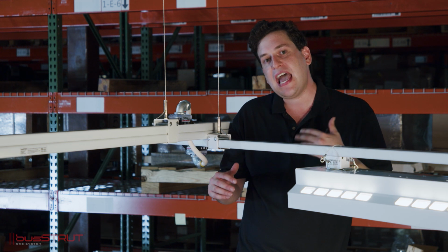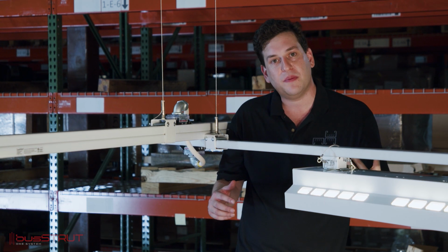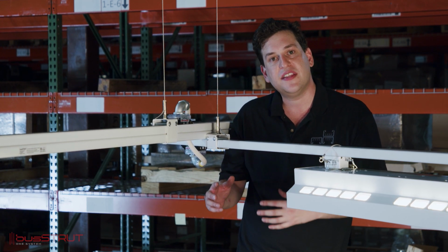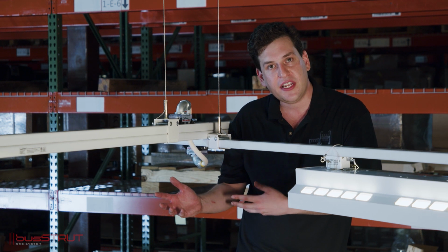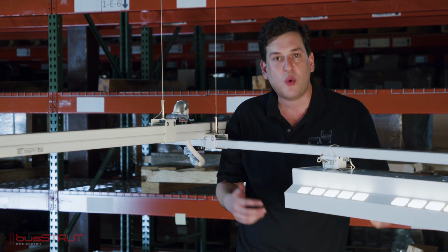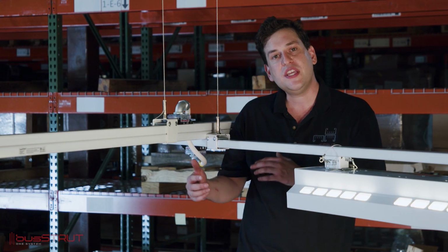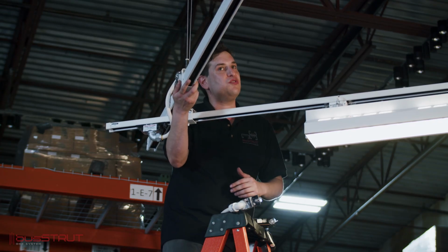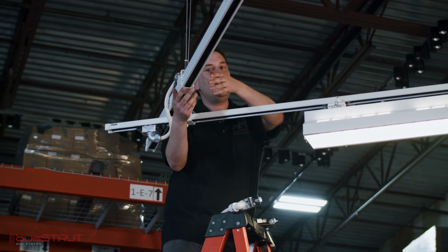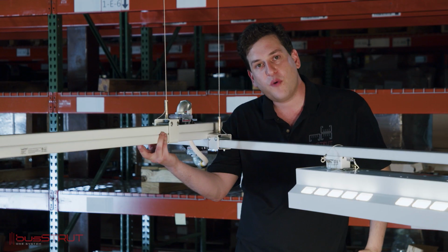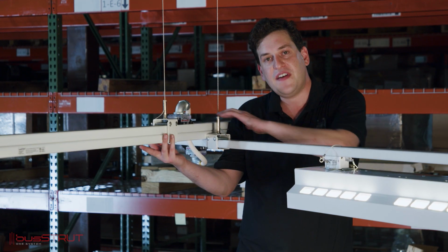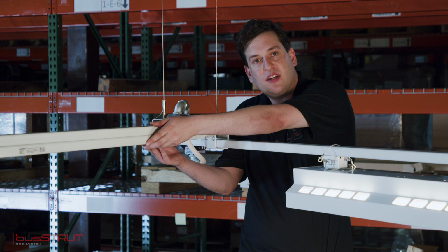But we have an added advantage as opposed to traditional busways. We have busSTRUT rated for 40 amps per circuit, and busSTRUT rated for 20 amps per circuit. We use the 40 amp rated busSTRUT, typically double decked, so you have up to 40 amp circuits fed along this double deck run.